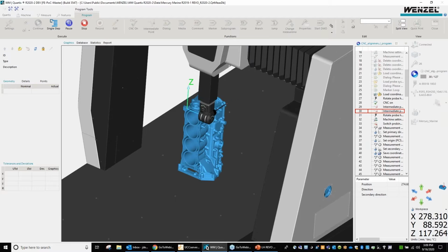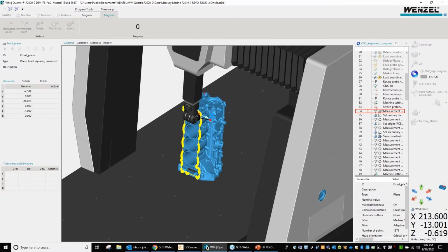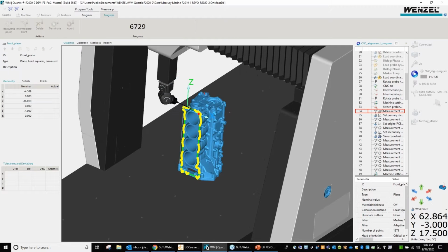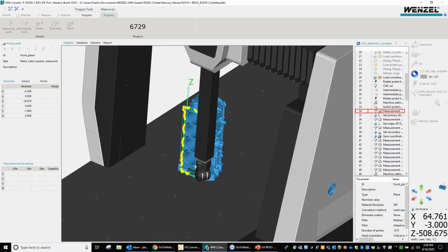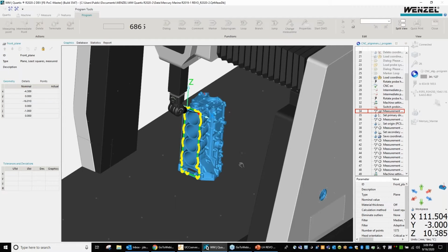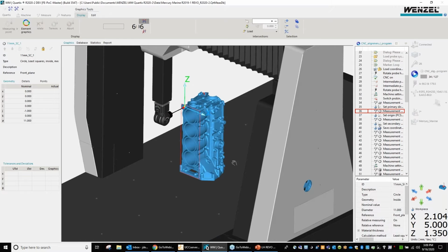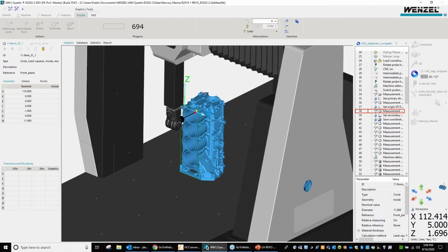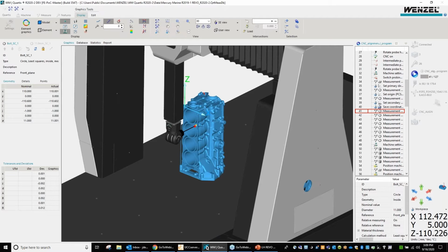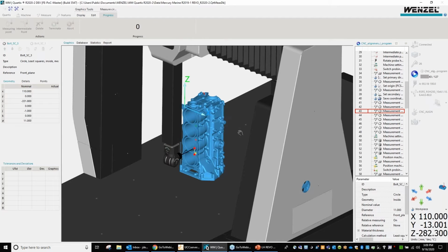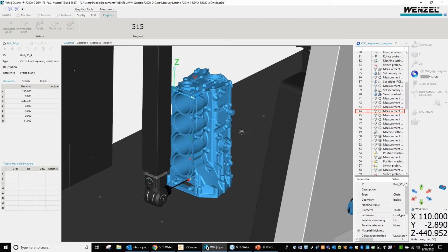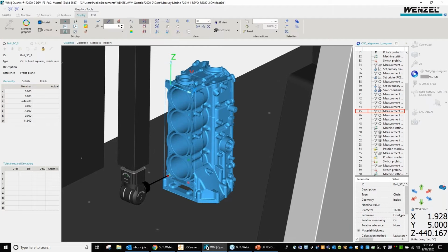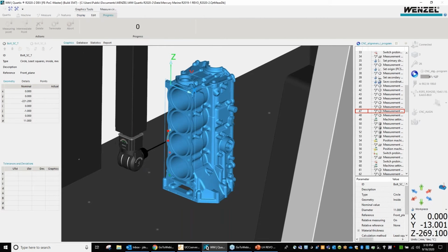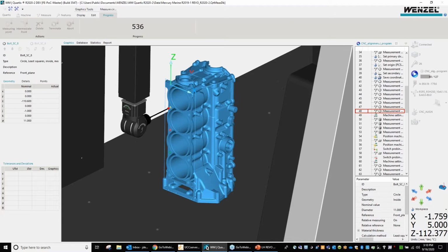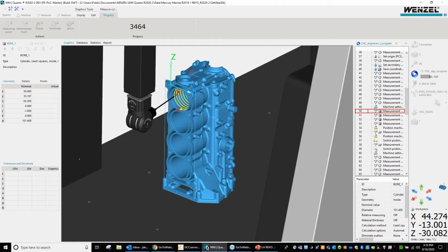So here the probe is locked, the machine is moving, the Y carriage probe rotates, and now it's doing all 5-axis type scanning. So here it can either keep the probe head locked and move the machine, or keep the machine locked and move the probe head. So here, as you notice on the screen, it's just doing a series of circular scans, very quick. Those aren't very big holes, but very fast scans, roughly around 400 points. And the point data you can choose to set as you set up your measurement.